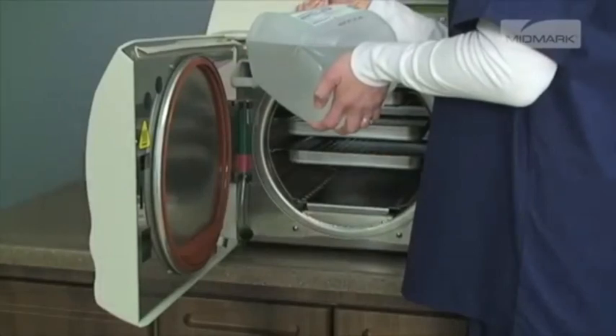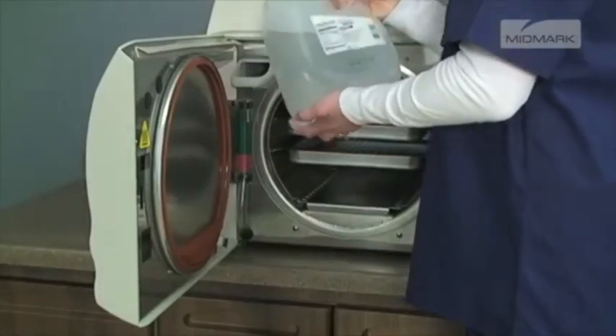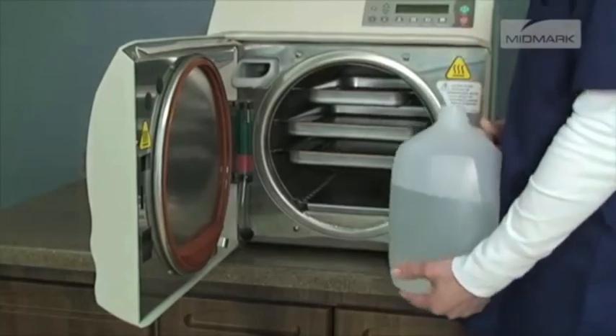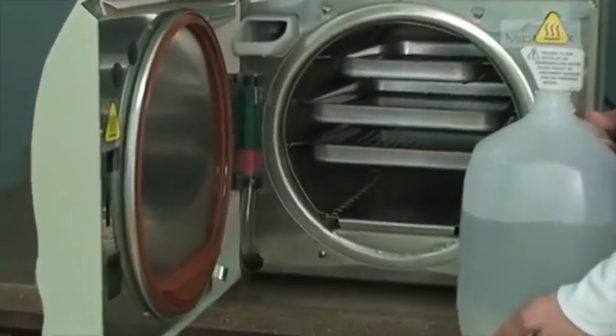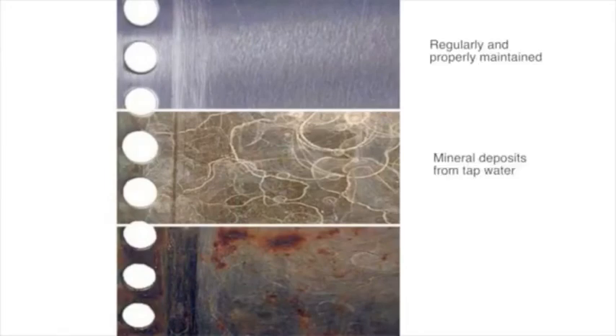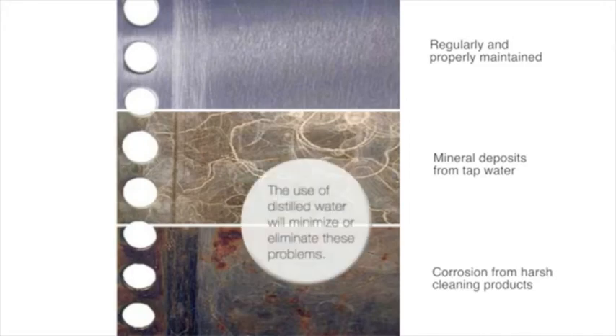It is very important that only distilled water be used. Since the autoclave operates with high water temperatures, any minerals dissolved in the water will leak out and form mineral deposits. This can prevent valves from opening or closing properly and can also lead to corrosion in the chamber and tubing. The use of distilled water will minimize or eliminate these problems.